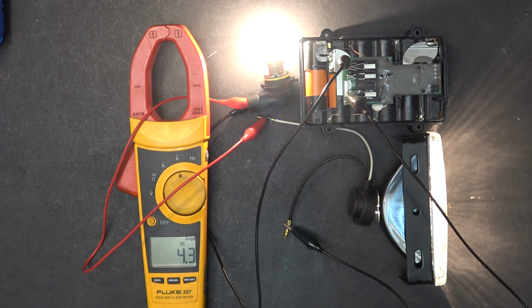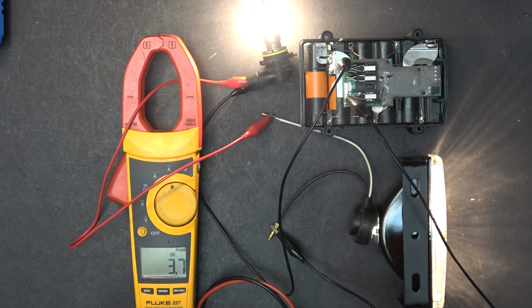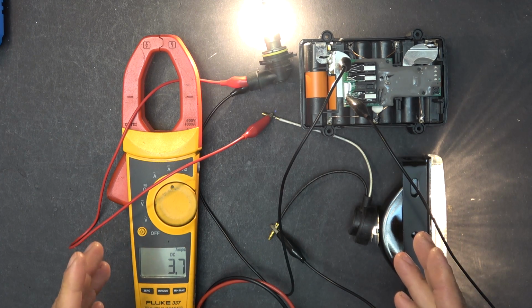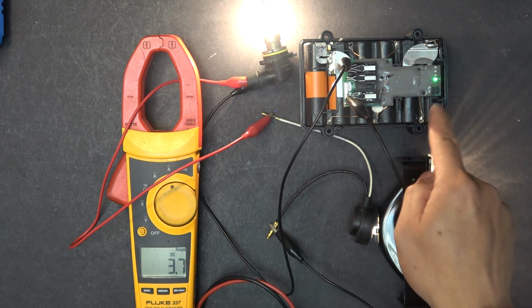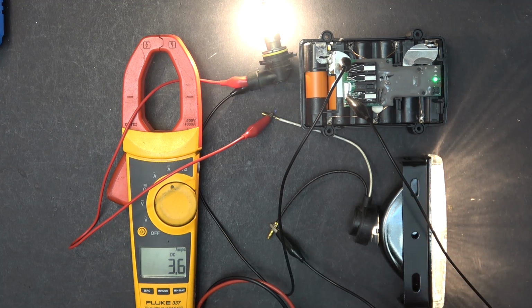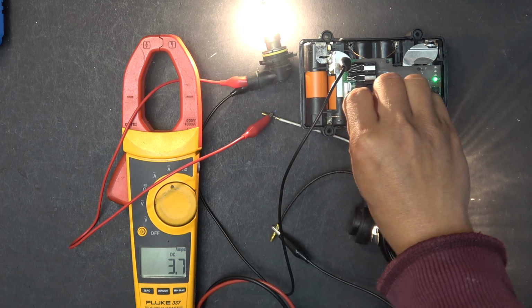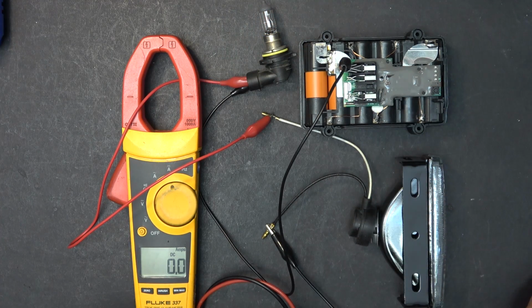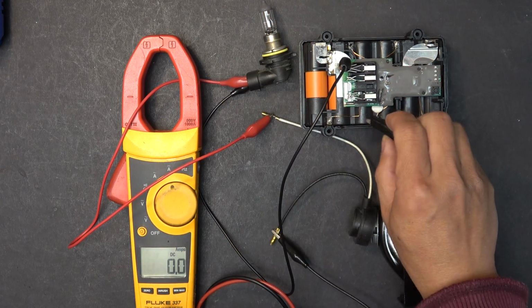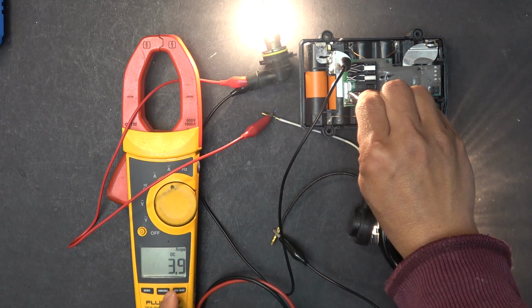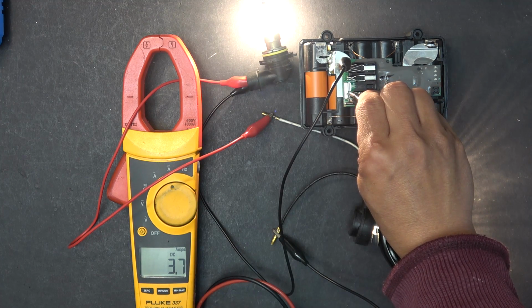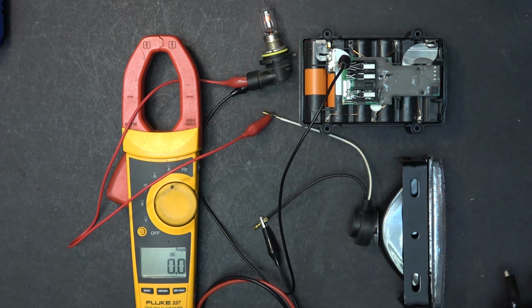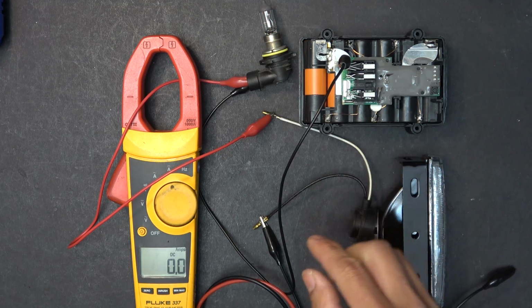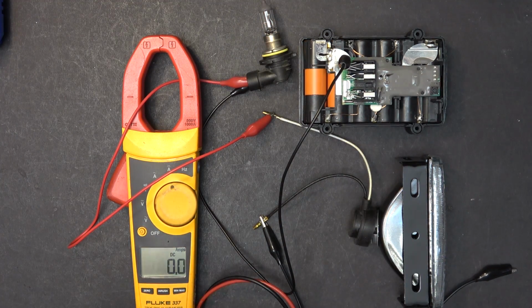I'll be right back. Alright, it's been about 45 minutes and we're down to 1 bar. So time to disconnect and check on the battery. You can see the current, it goes down to 3.7 amps, 3.8 amps instead of 4.3 amps. And that's because as the voltage goes down, the current also goes down.